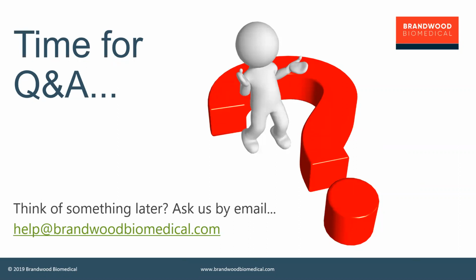Any idea on when the new Part 1 standard will be recognised by FDA and added to the EU list? Well, we talked about the EU one, but you mentioned earlier that FDA have now actually recognised the Part 1. That's right. It's a very interesting recognition because often FDA will only partially recognise a standard, and they always nominate the bits that they're not going to recognise and the reasons for it.